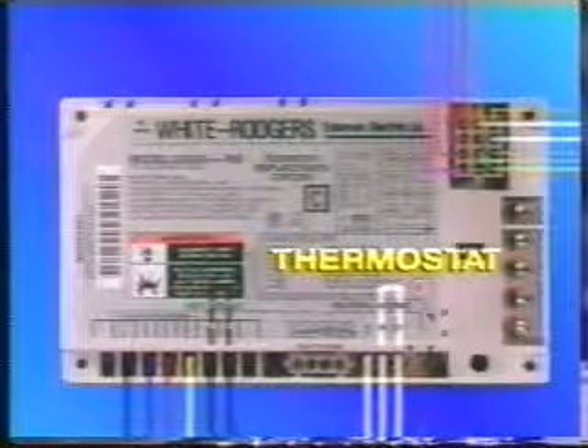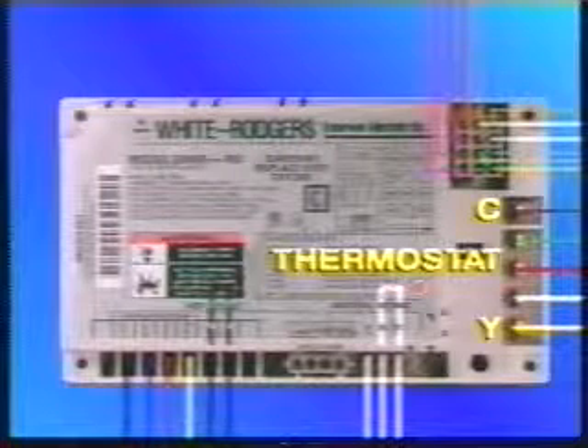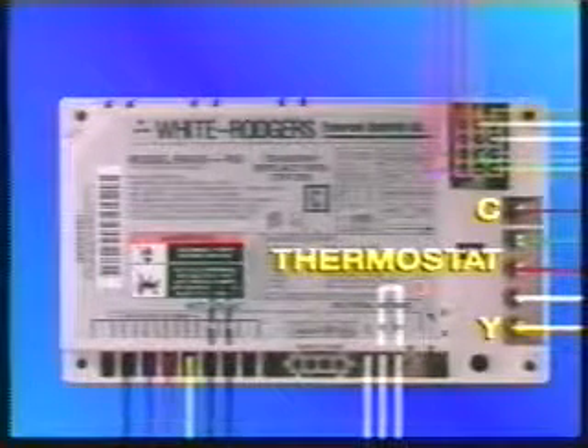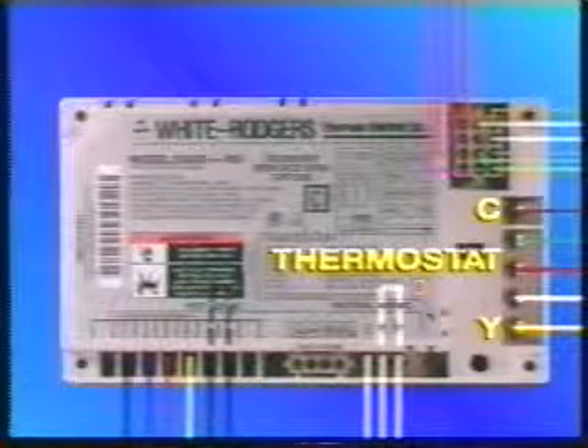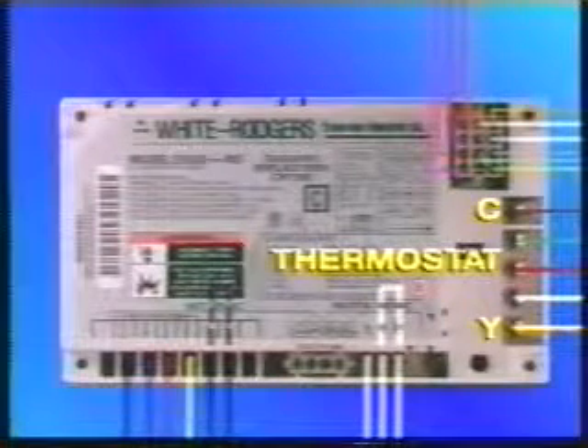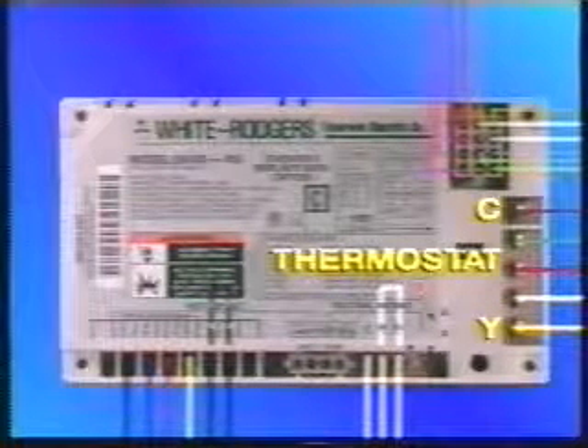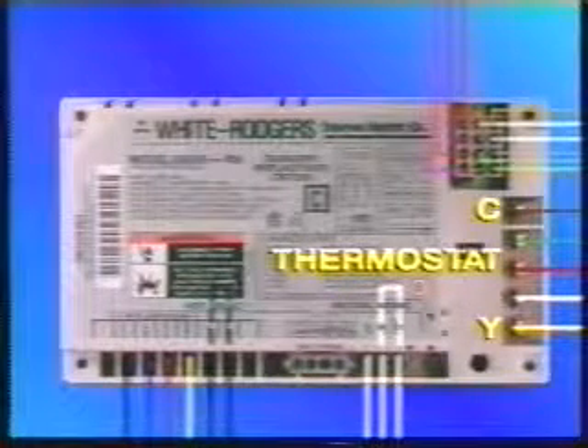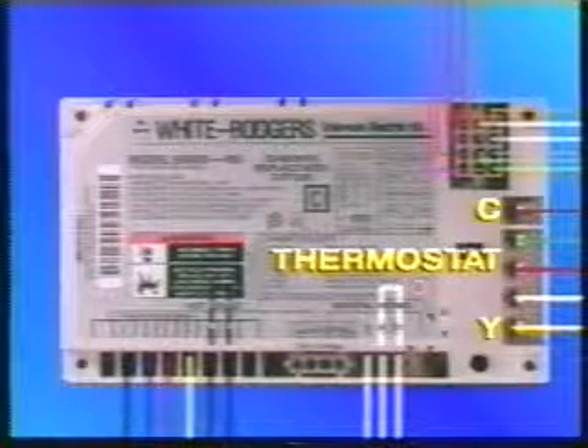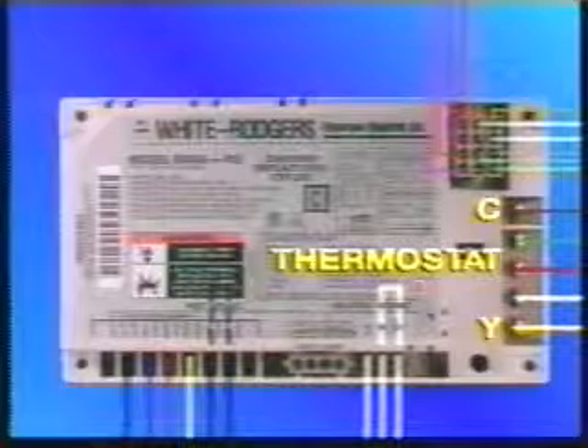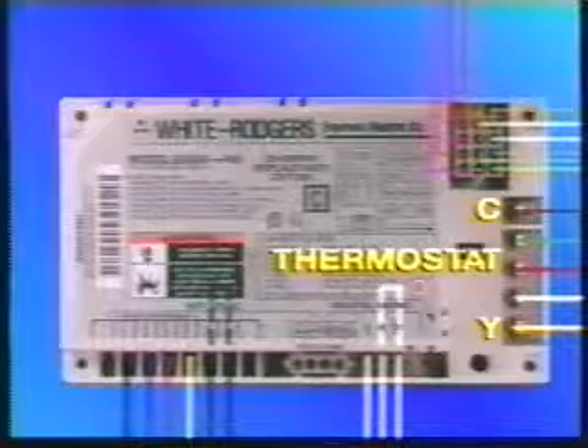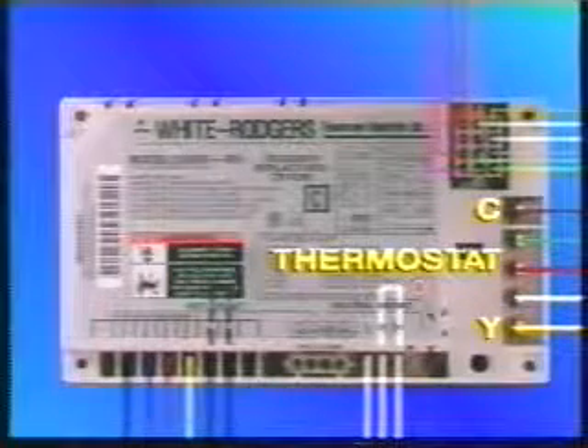The thermostat connections are made to the screw terminals on the board. Coding follows industry practice. The compressor contactor leads are connected to the Y and common terminals. Note that this puts the cooling contacts of the thermostat in control of the compressor. The compressor contactor is powered with 24 volts anytime there is a call for cooling from the thermostat. It is important to understand that the compressor contactor leads must be connected to the module in order to obtain cooling fan speed.